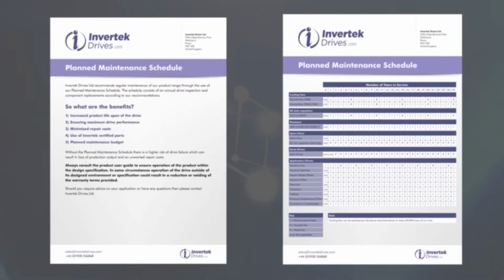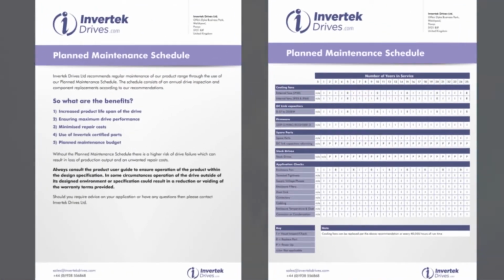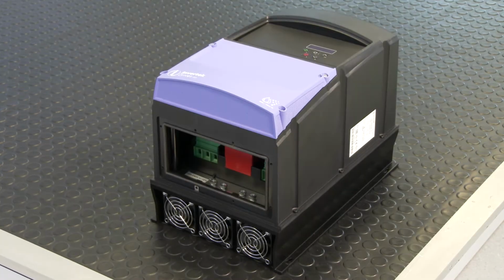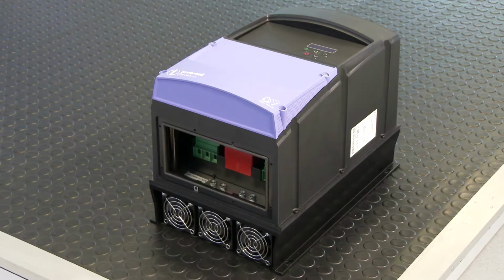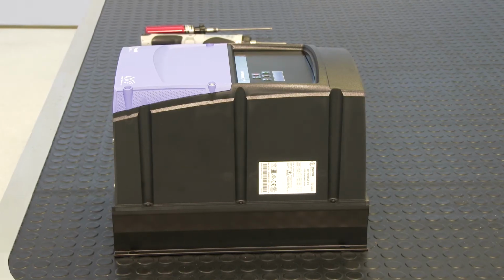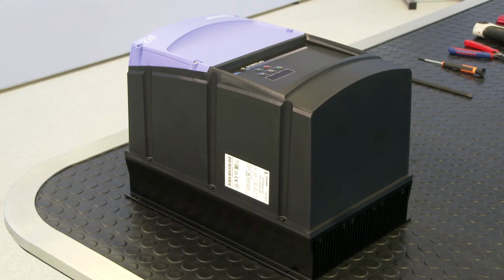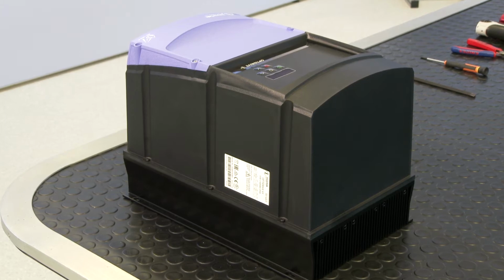This video shows how to replace the internal cooling fan, heatsink cooling fans and DC capacitor board on an ODE3 IP66 outdoor frame size 4 as part of the planned maintenance schedule. Place the drive on a flat surface that will prevent damage and allow easy access to internal parts. Ensure anti-static precautions are always taken.